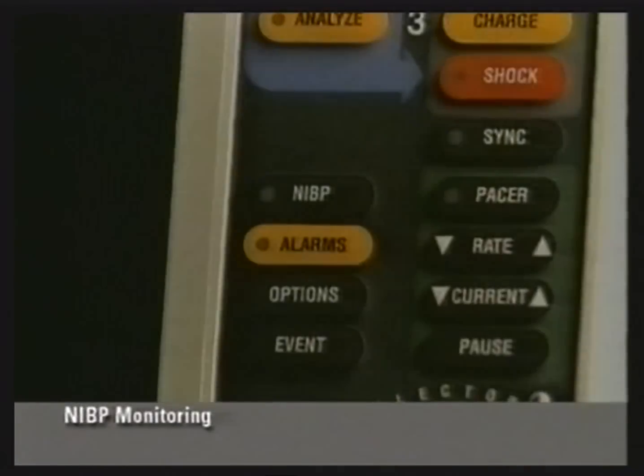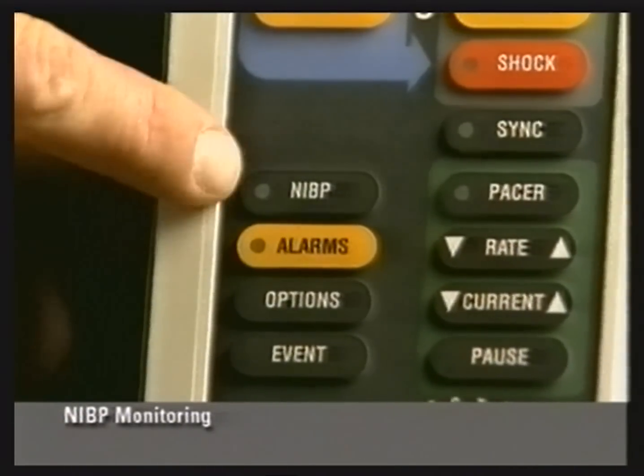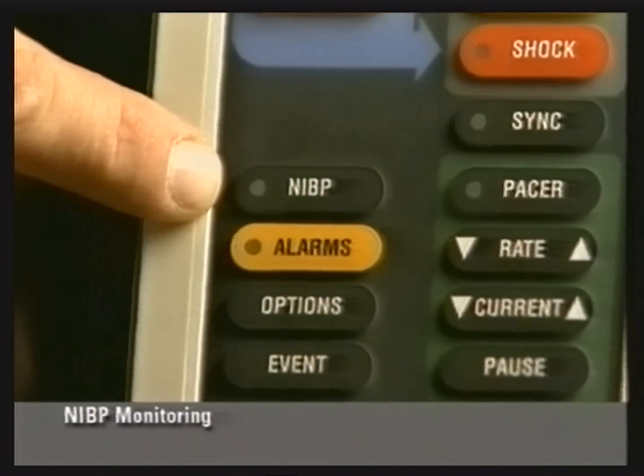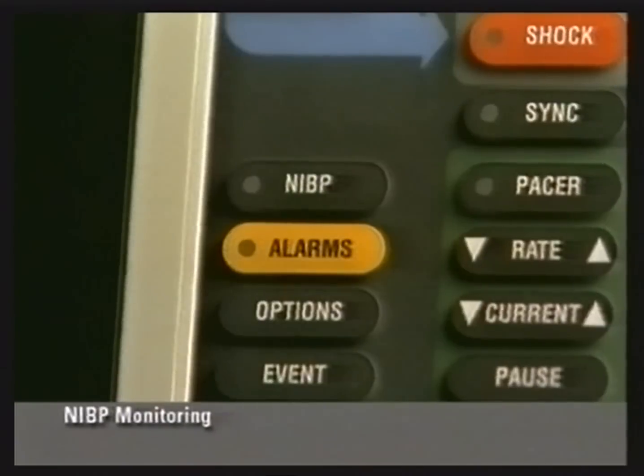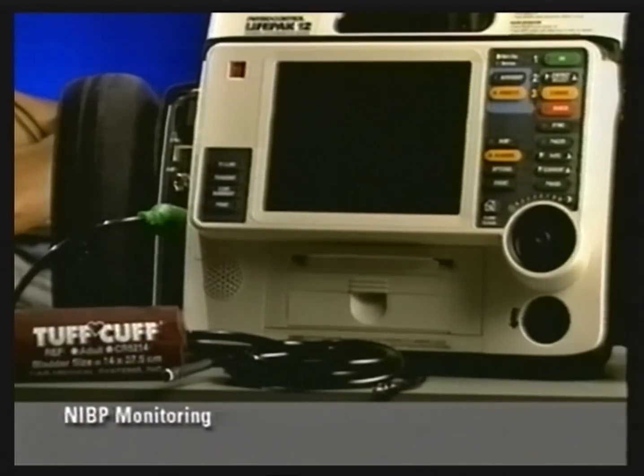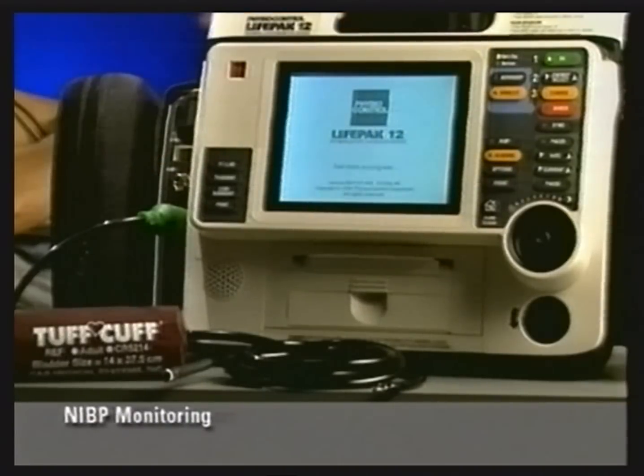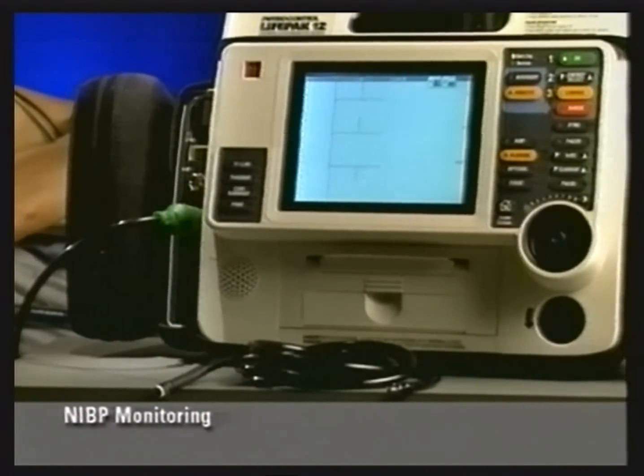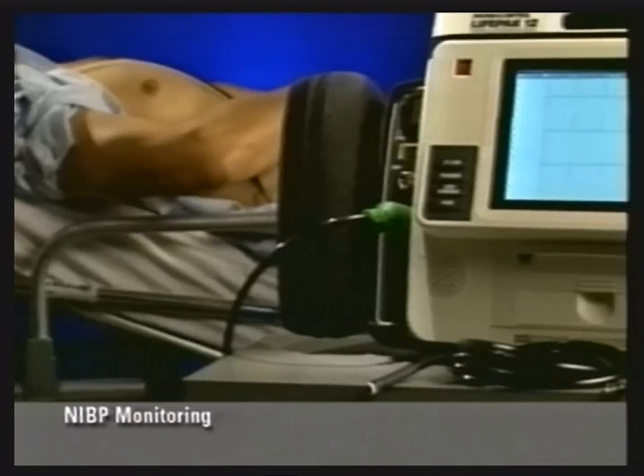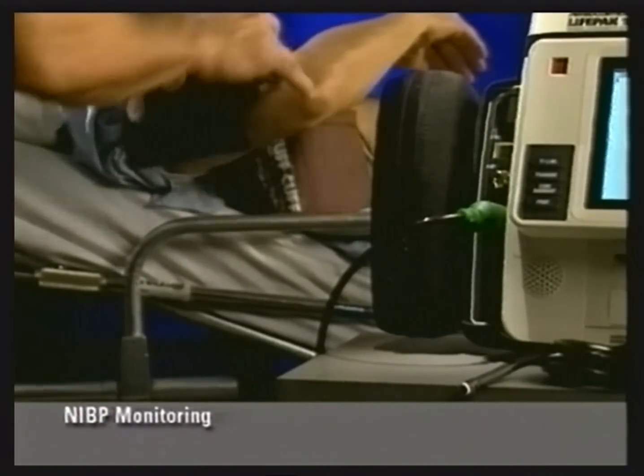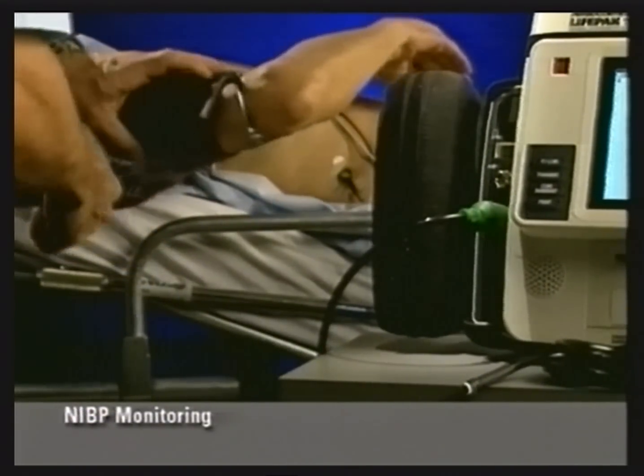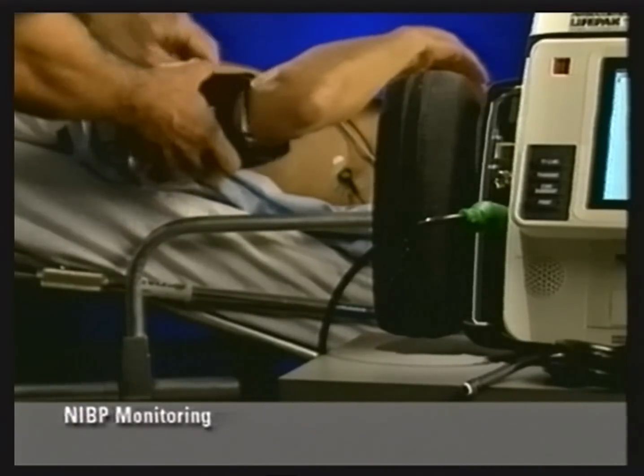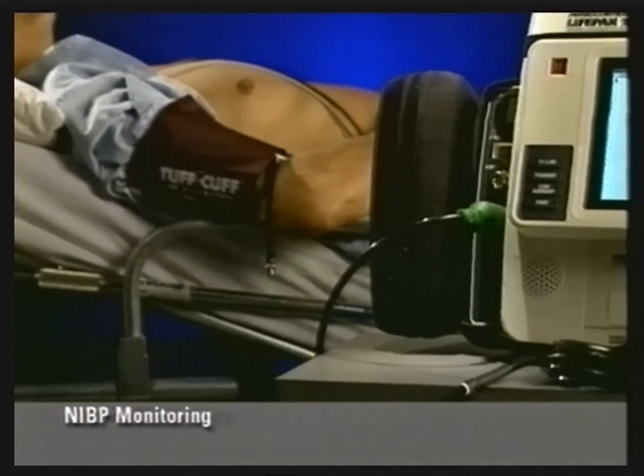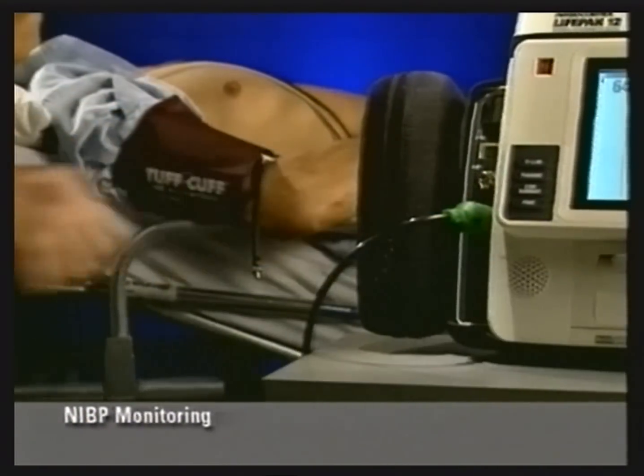The non-invasive blood pressure monitor is another helpful tool that can be used to automatically measure the blood pressure of an adult or pediatric patient. To use the NIBP monitor, power on the monitor and adjust the contrast if necessary. Select the appropriate size blood pressure cuff and apply it snugly to the patient's extremity. The exact position of the cuff is not important because the cuff provided by Physio does not have a bladder and inflates completely around the extremity.